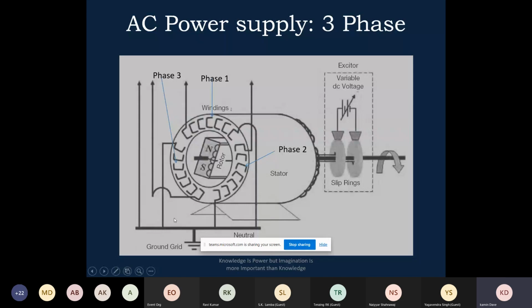In a small machine, it will be solidly grounded. For an intermediate machine, something like 20 megawatt, 30 megawatt machines, it will be NGR grounding. And then 100 megawatt machines, 250 megawatt machines, it will be grounding through an NGT with NGR. So grounding depends on the networks, fault calculation, and other parameters. But yes, this is how we can do the grounding with the second end of the coils.